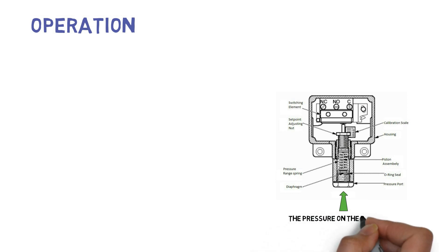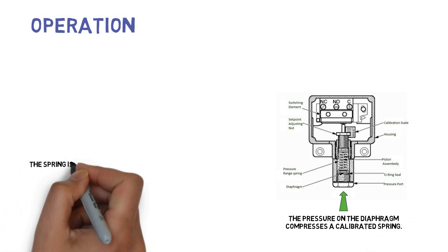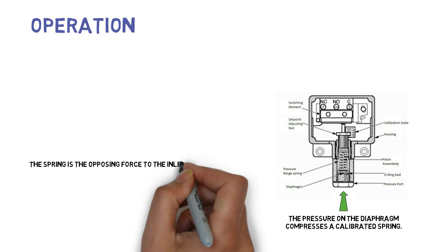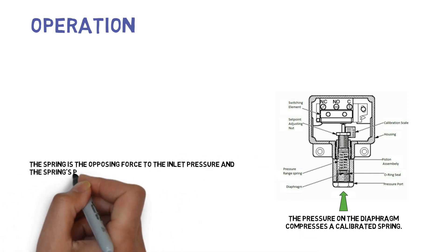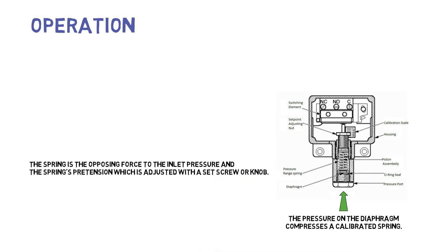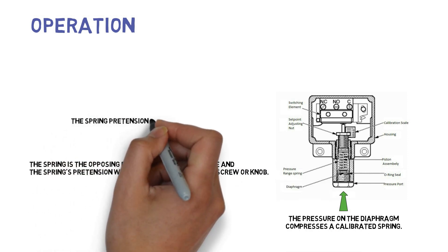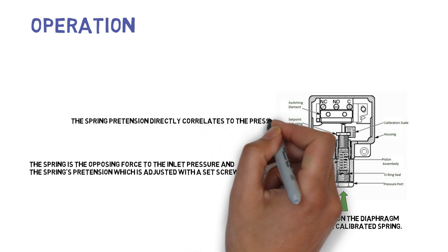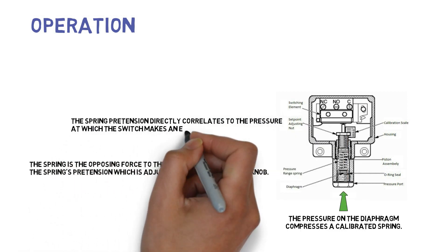The pressure on the diaphragm compresses a calibrated spring. The spring is the opposing force to the inlet pressure, and the spring's pretension is adjusted with a set screw or knob. The spring pretension directly correlates to the pressure at which the switch makes an electric contact.